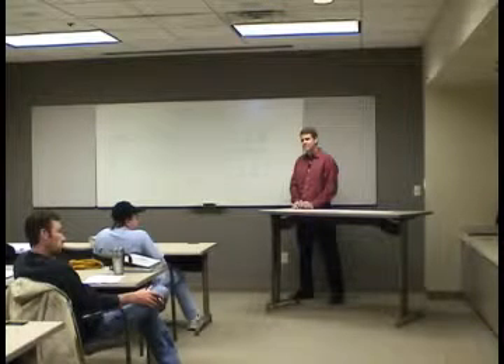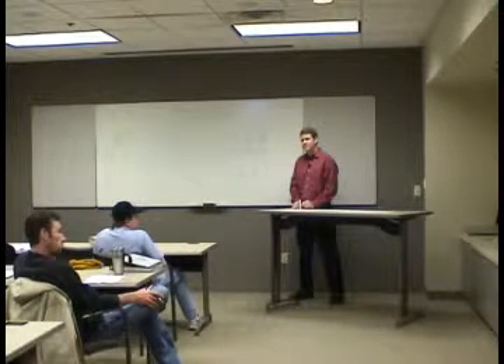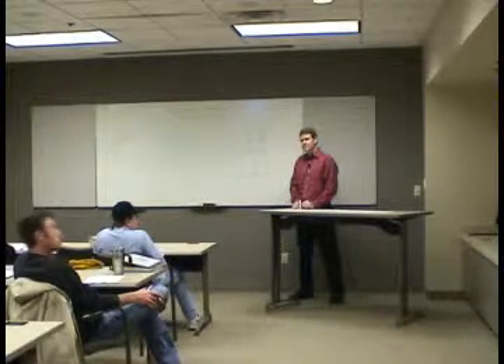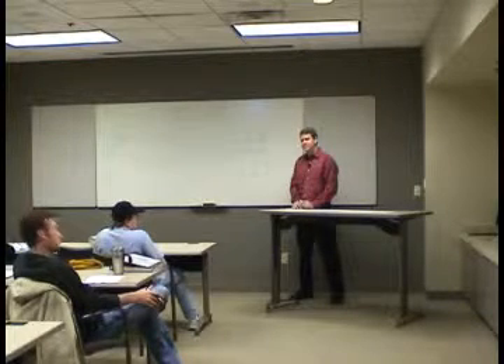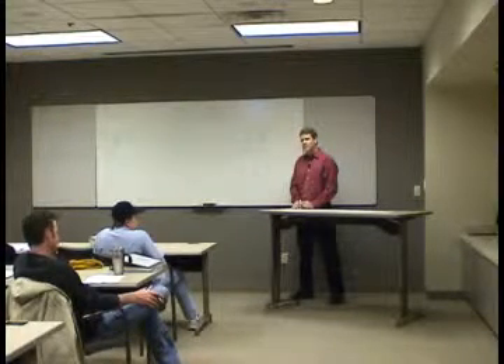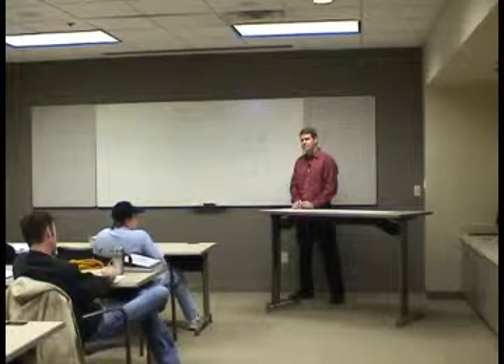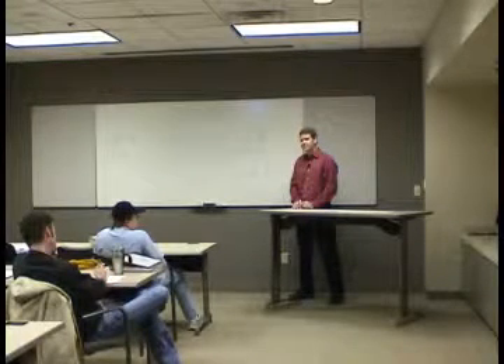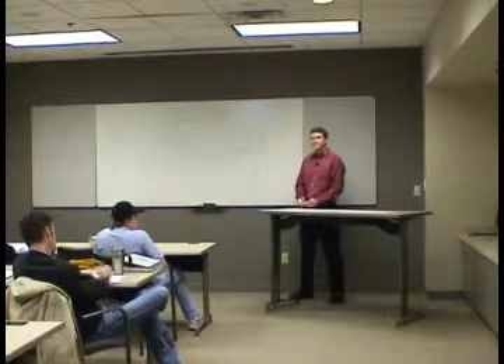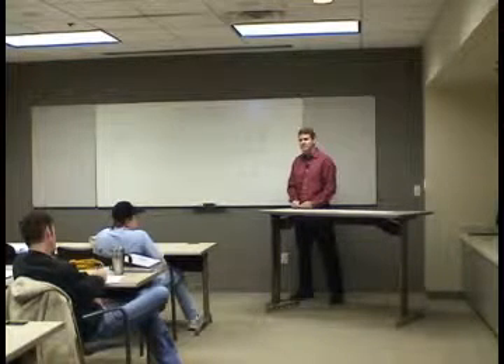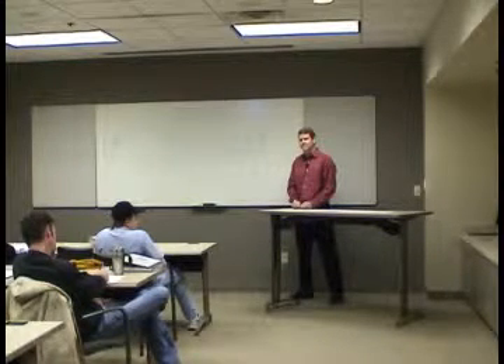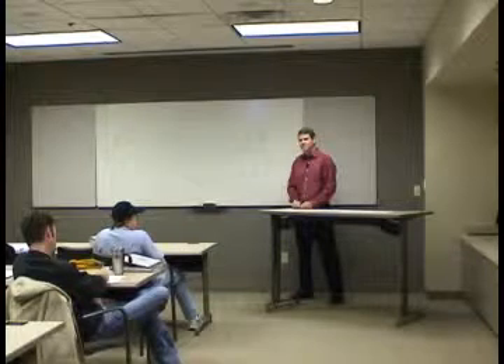So if you're trying to pump 140 degrees out of that diffuser, it's just going to turn around and go right back upstairs because it's going to say, screw this, I'm really buoyant. I have a lot of energy here. I'm going to just go back up the other way. And so the trick is to get that delta T between set point and coming out of the diffuser as close as you can to 15 degrees or less. And that'll give you a better mix.